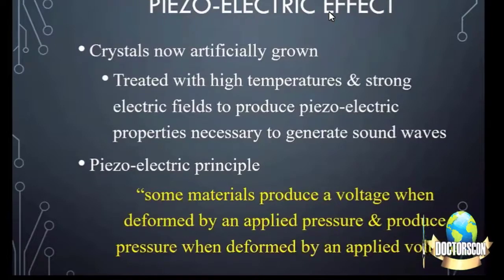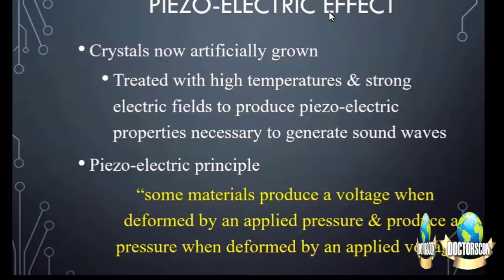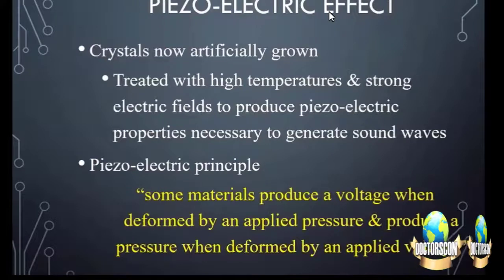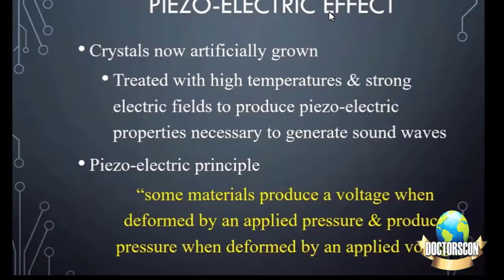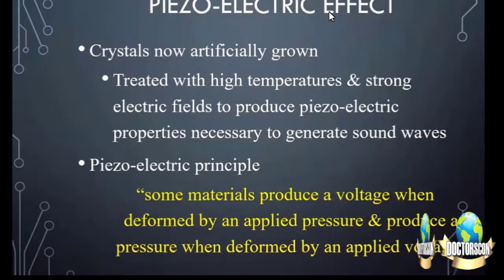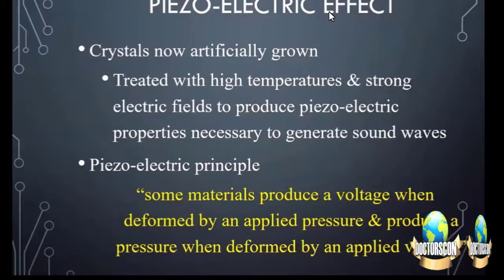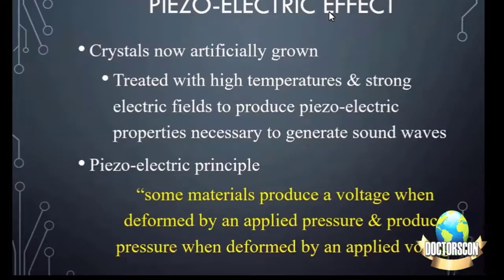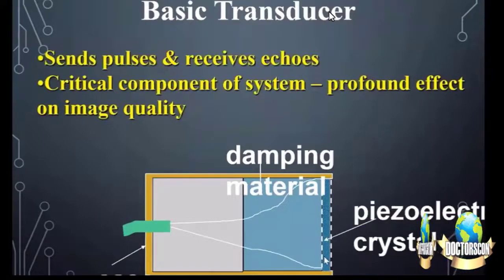This is how it works, depending on polarity of voltage applied. So the crystals expand or they contract. They are placed in this form and they move in a sequence in a specific way. So they are not practically striking with each other to produce sound. They are placed at a distance which is of micro level, and due to change of the polarity, they move. The basic transducer has got different structures. It sends pulses and receives echoes. Here is the housing which has got piezoelectric crystals, and this part of the transducer is in touch with the body of the patient, having a gel in between.